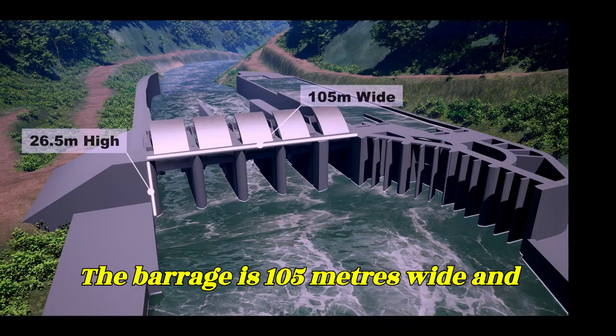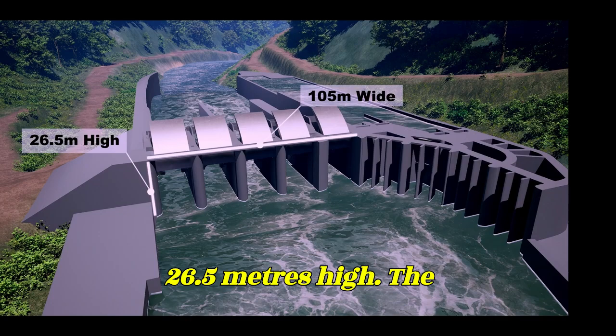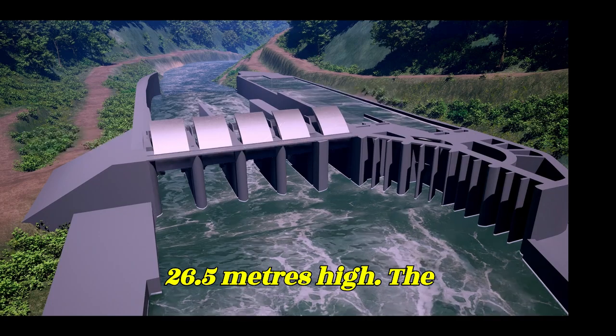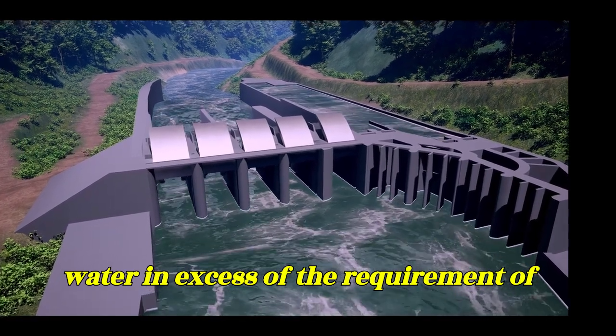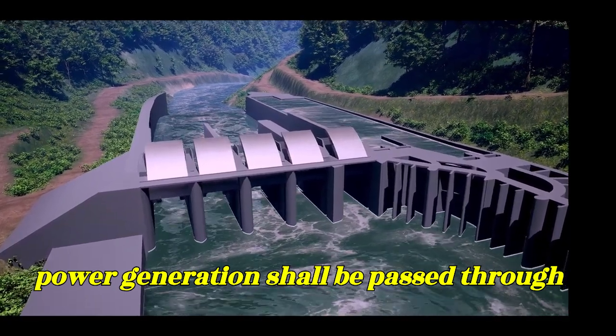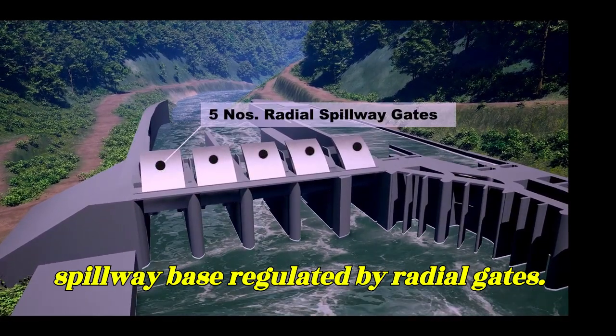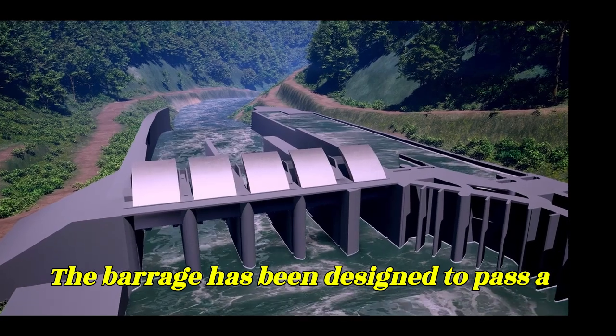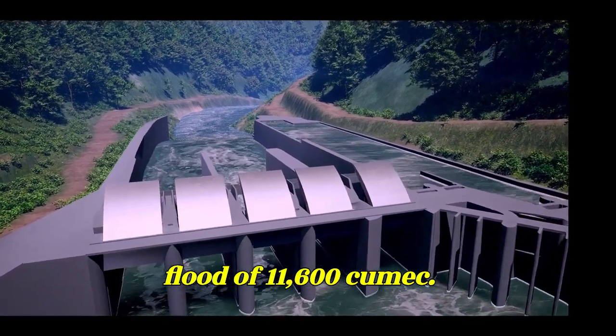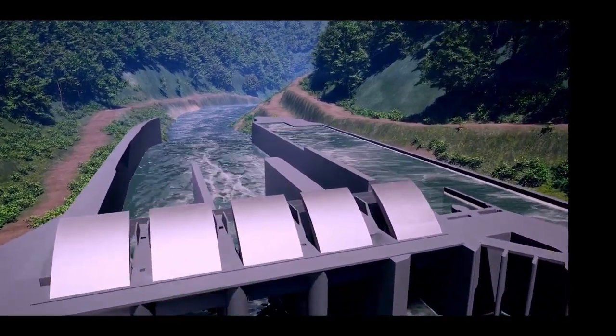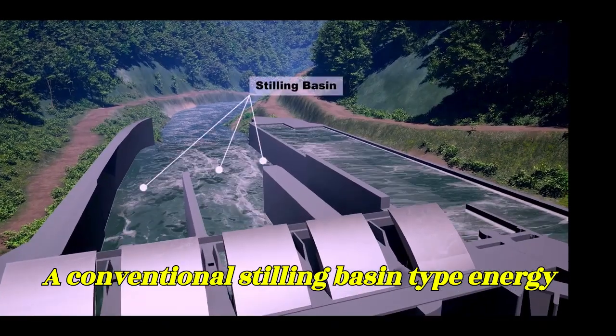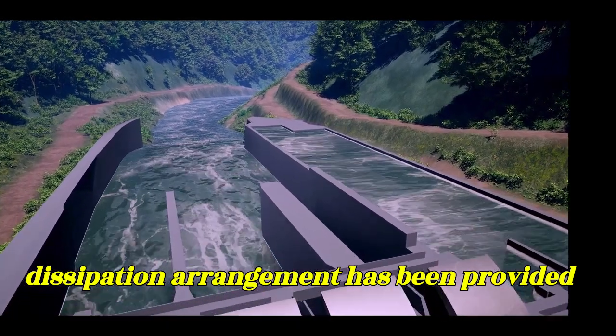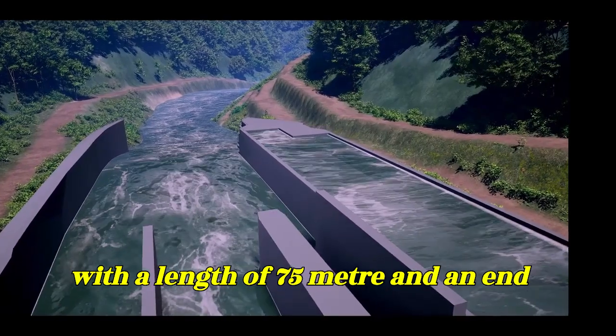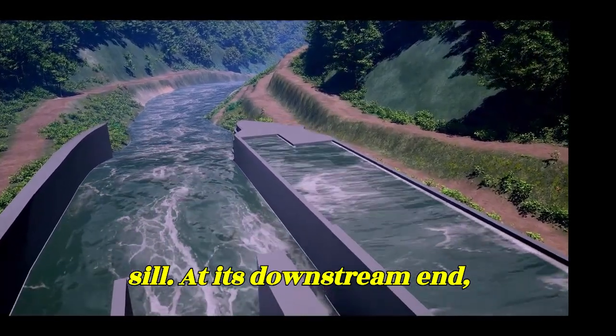The barrage is 105 meters wide and 26.5 meters high. The water in excess of the requirement of power generation shall be passed through spillway bays, regulated by radial gates. The barrage has been designed to pass a flood of 11,600 cubic meters per second. A conventional stilling basin type energy dissipation arrangement has been provided with a length of 75 meters and an end sill at its downstream end.